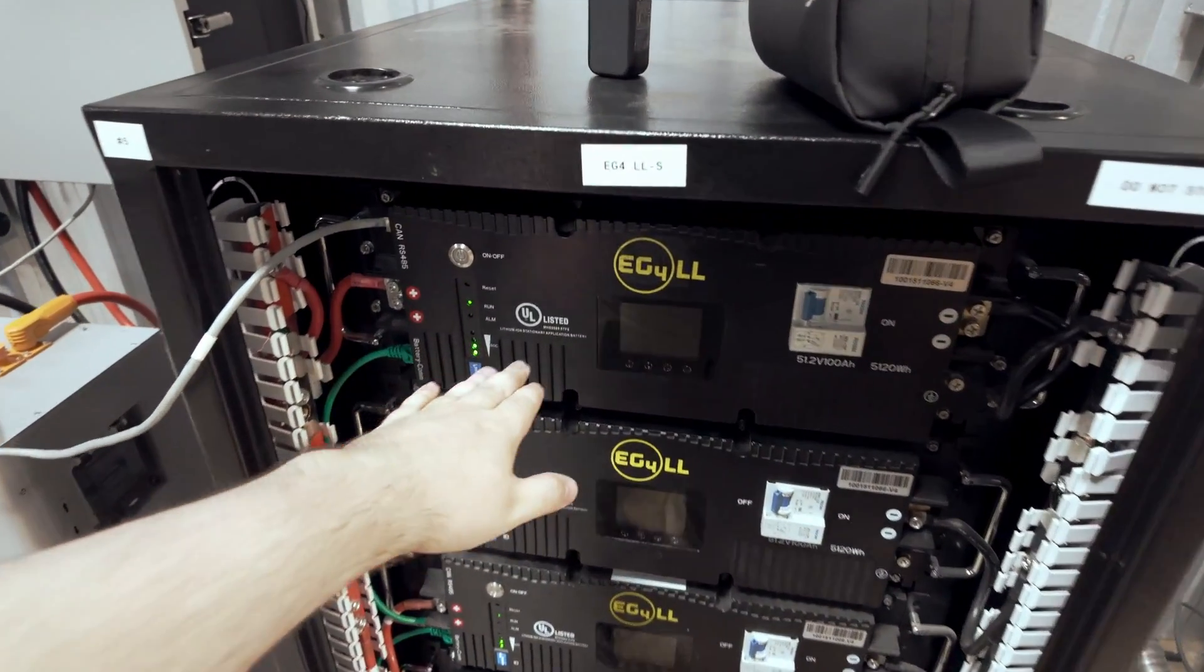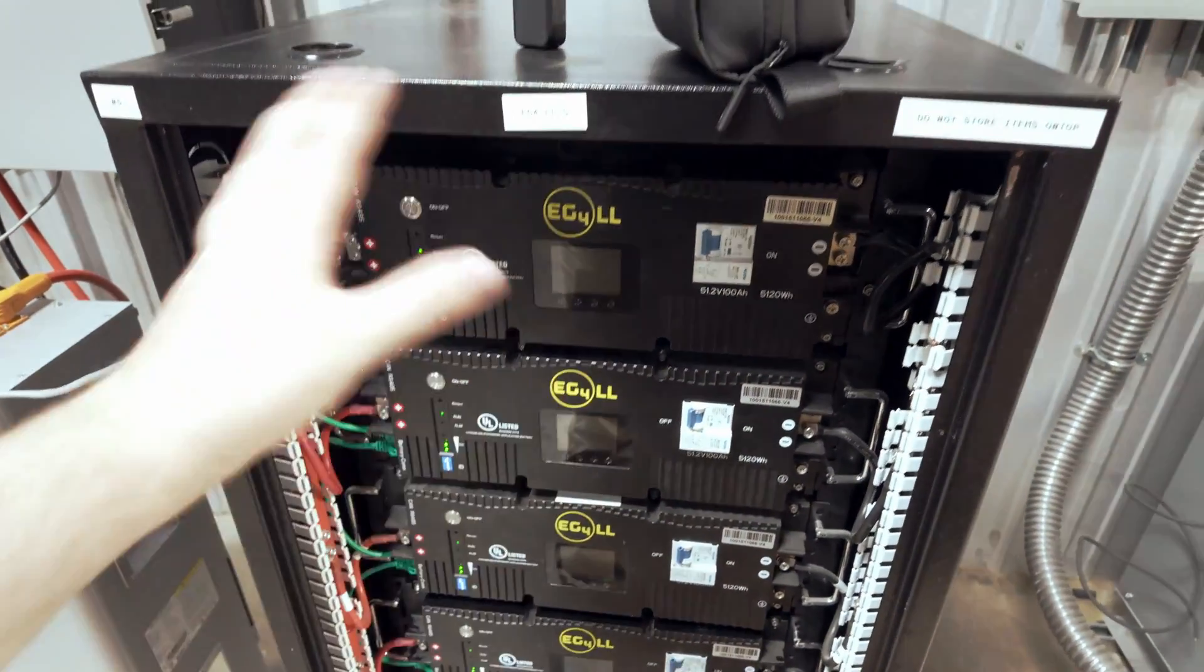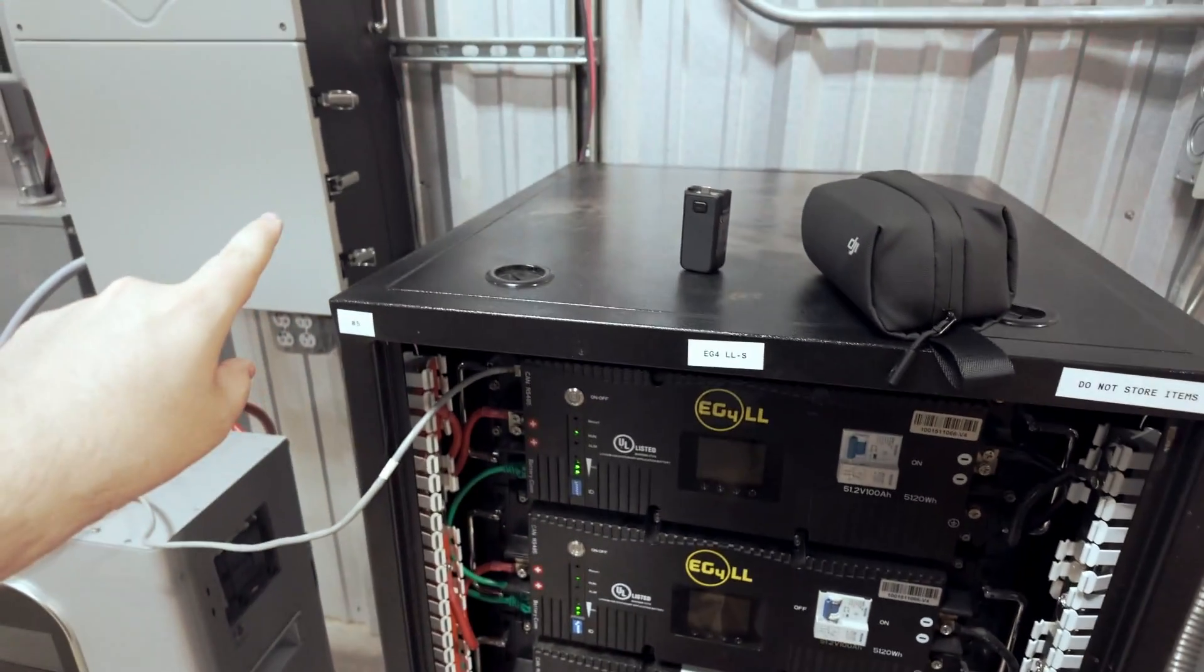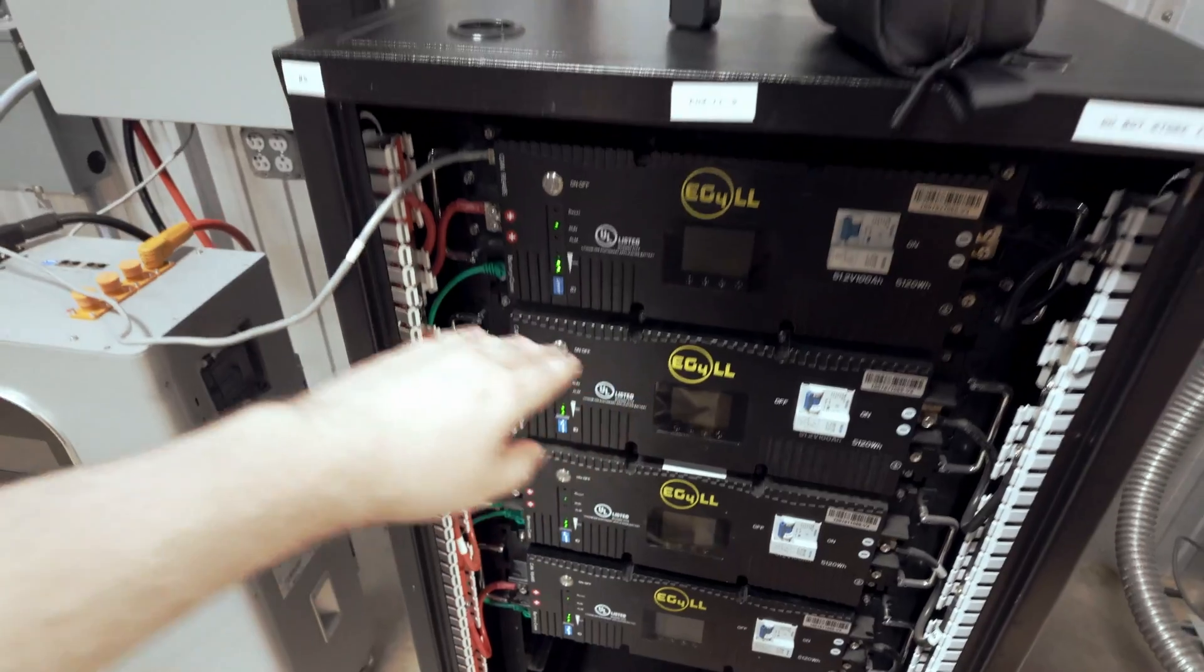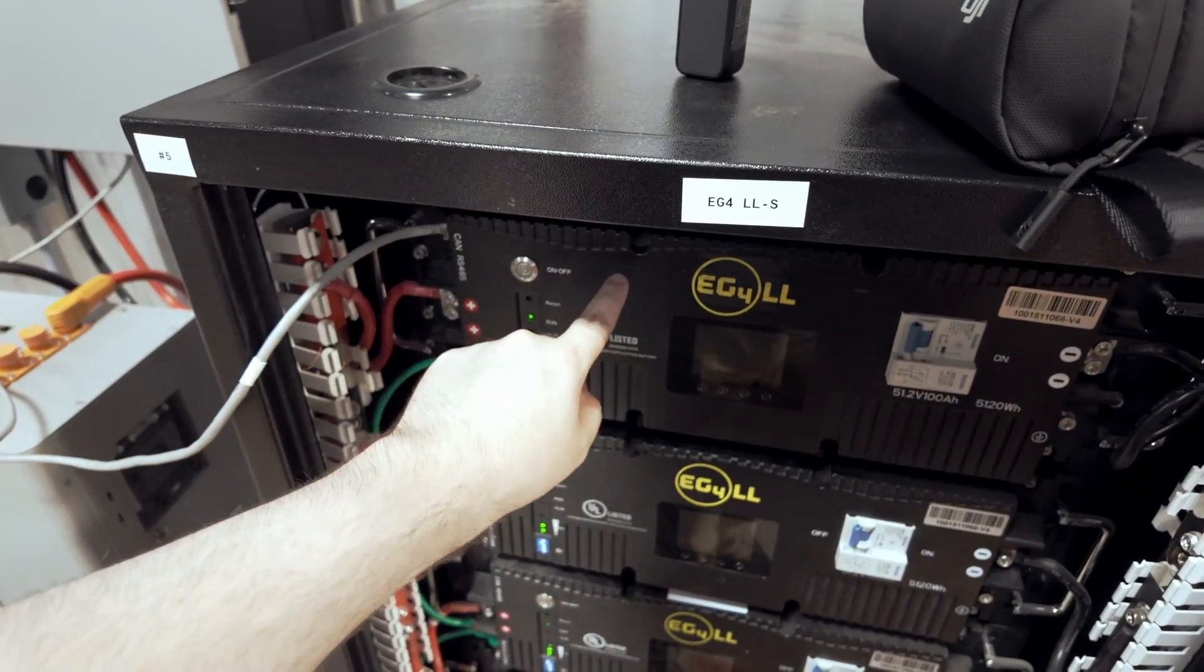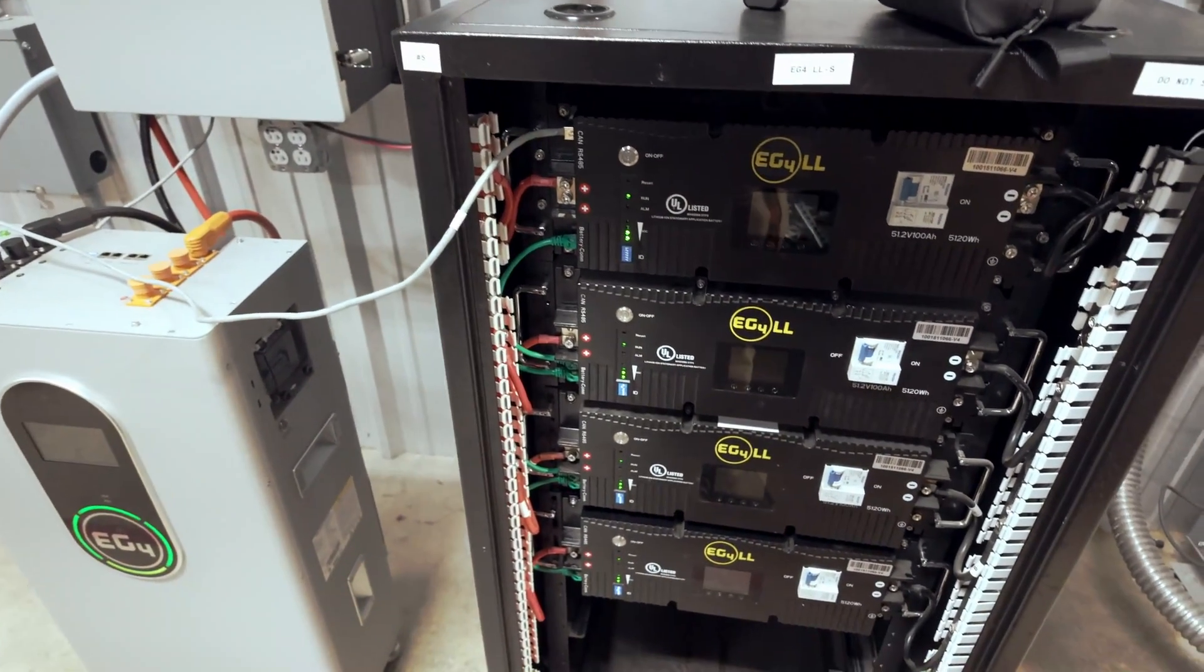One thing to note with the LL batteries is if you had to change your protocol on your master battery during the setup of the system and you don't do it all at once, your master battery may only communicate the first couple of batteries that are online to the Solark.